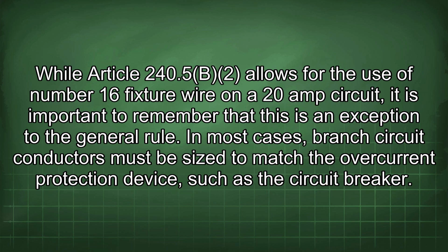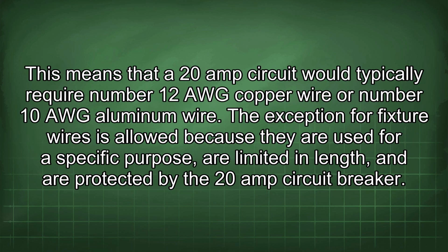In most cases, branch circuit conductors must be sized to match the overcurrent protection device, such as the circuit breaker. This means that a 20 amp circuit would typically require a number 12 AWG copper wire or number 10 AWG aluminum wire. The exception for fixture wires is allowed because they are used for a specific purpose, are limited in length, and are protected by the 20 amp circuit breaker.